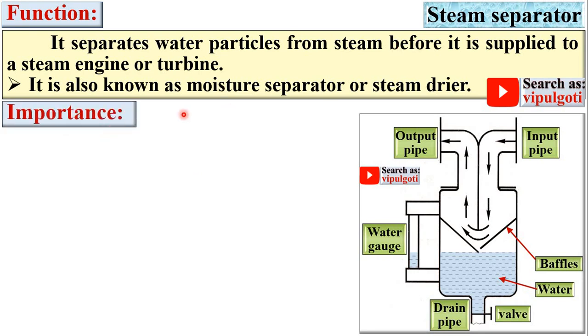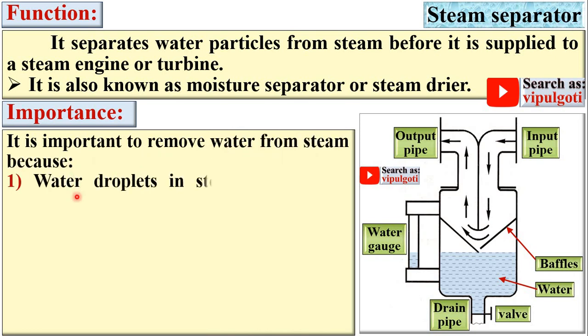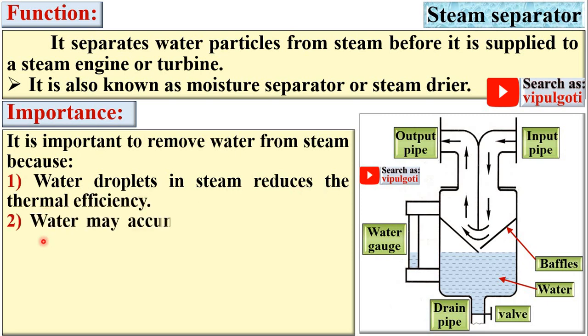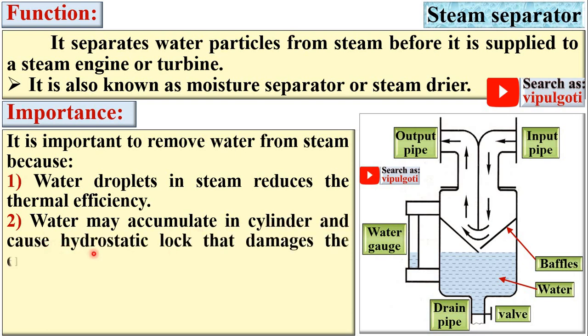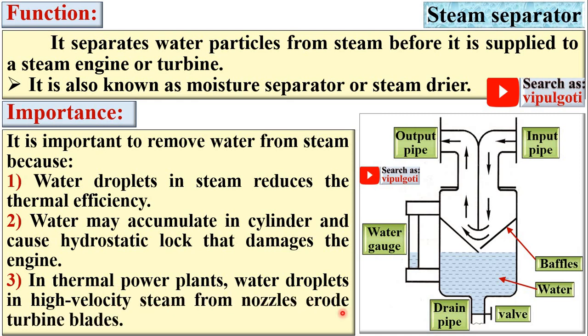Importance of the steam separator: It is important to remove water from the steam because water droplets in steam reduce the thermal efficiency. Water may accumulate in the cylinder and cause hydrostatic lock that damages the engine. In thermal power plants, water droplets in high velocity steam from the nozzles also erode turbine blades.